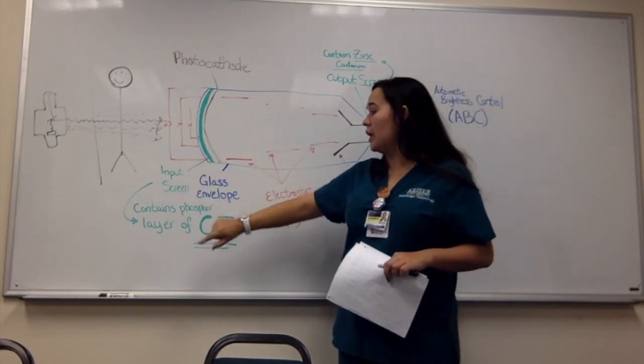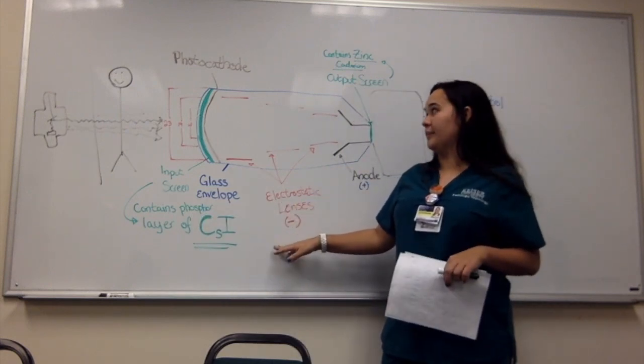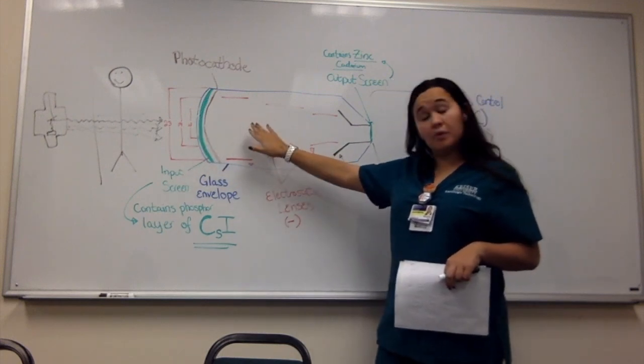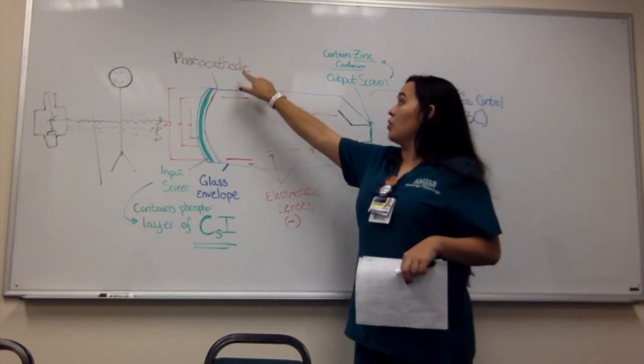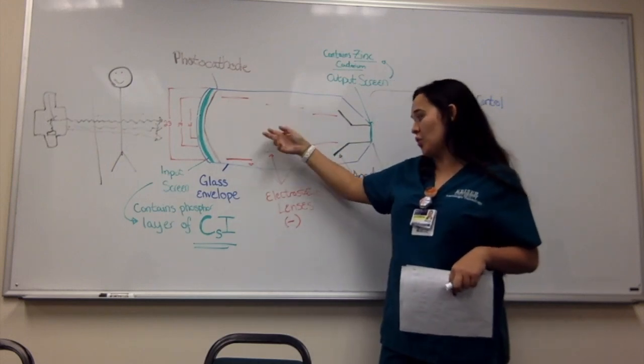So the input screen contains a phosphor layer of CSI, which is also known as cesium iodide. Once it gets the photons, it turns it into light photons, and it goes to the photocathode. The photocathode gets the light photons and turns it into electrons.